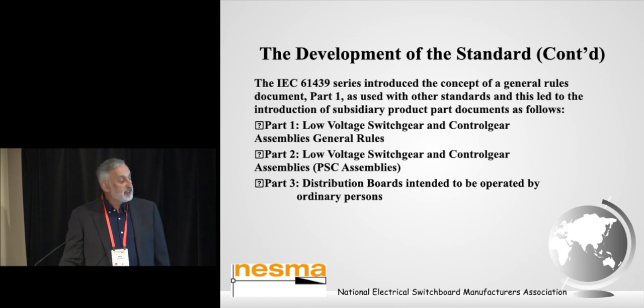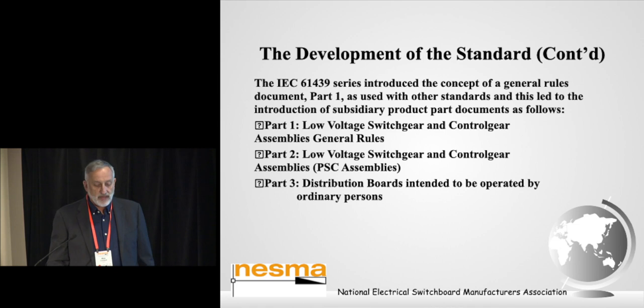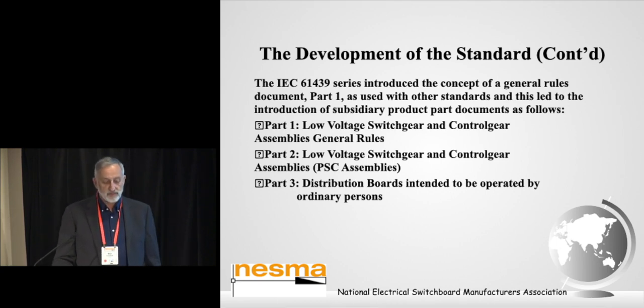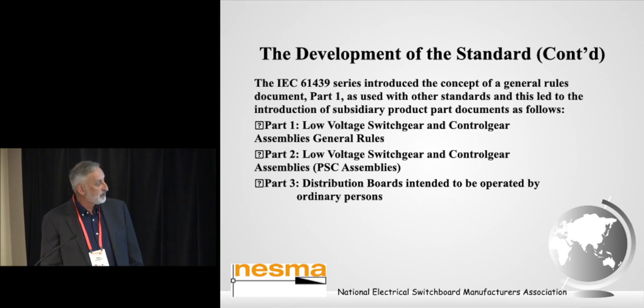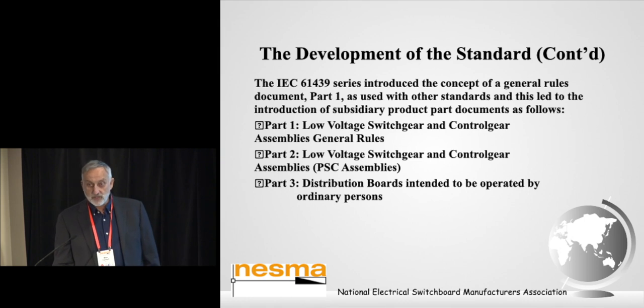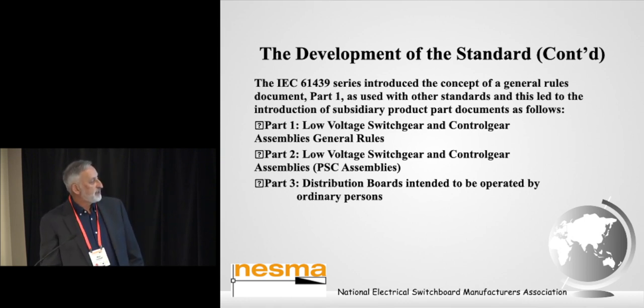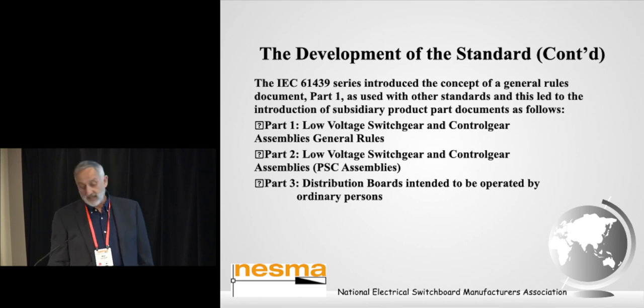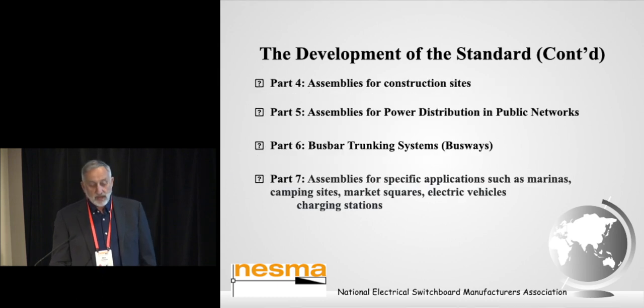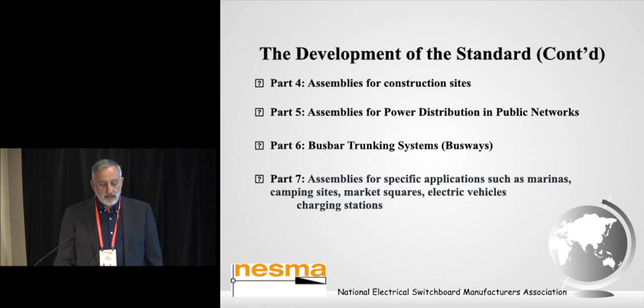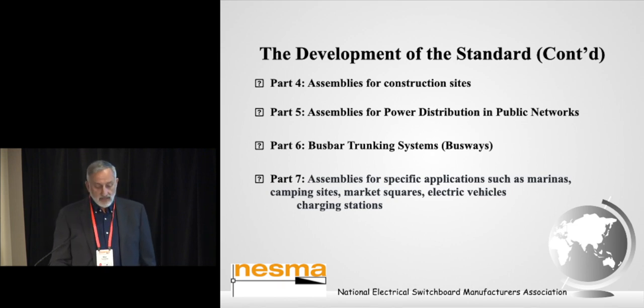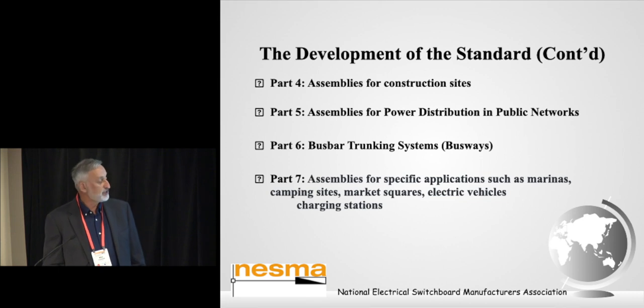The IEC 61439 series introduced the concept of a general rules document, or Part 1, as used by other standards, and then this led to the introduction of the subsidiary product part documents as follows. So we have Part 1, which is the general rules. Part 2 is the actual document you're building your switchboard to, which is the low voltage switchgear and control gear assemblies, or the PSC assemblies. And then Part 3 covers the distribution boards intended to be operated by ordinary persons. Part 4 is assemblies for construction sites. And Part 5, assemblies for power distribution in public networks. Part 6 becomes the busbar trunking. And then the assemblies for specific applications such as marinas and electric vehicle stations are found in Part 7.